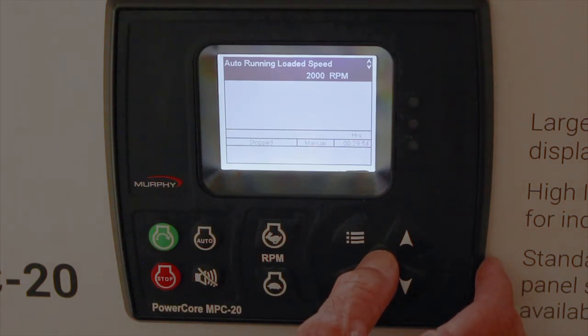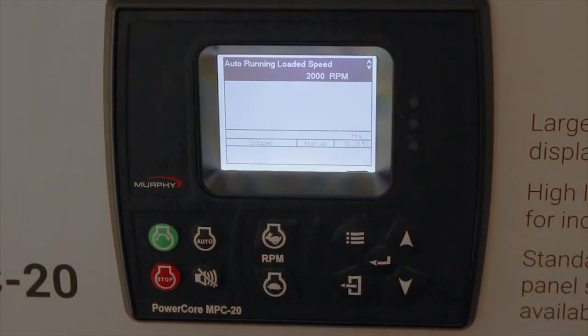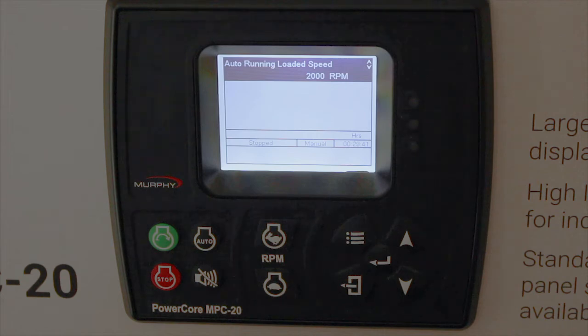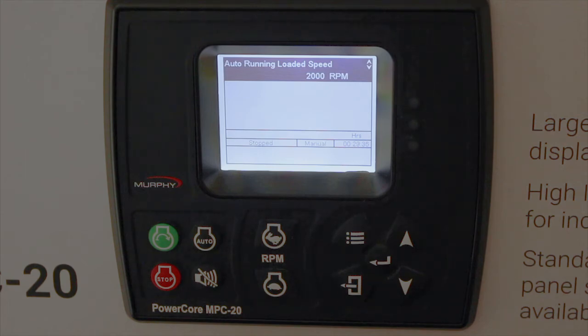Auto running loaded speed defaults to 2000 RPM, but you can change that. Keep in mind that the maximum RPM set point covered in the previous video overrides the auto running loaded speed. So if you had a lower maximum RPM than the running loaded RPM, it will only go to the maximum — the maximum overrides this setting.